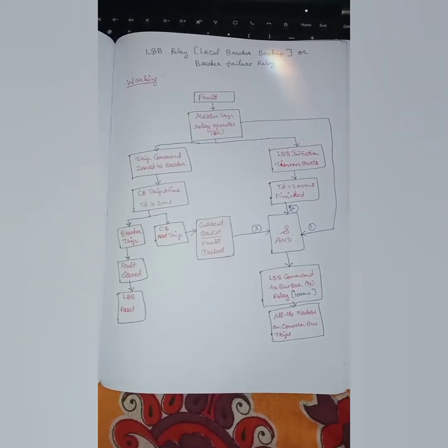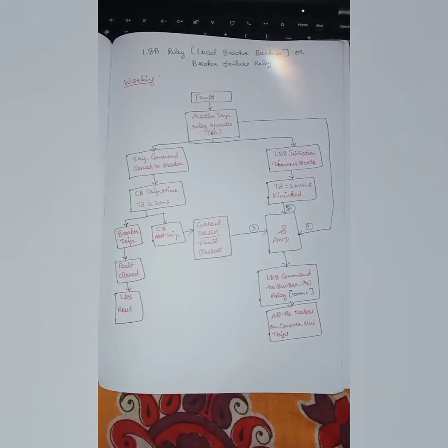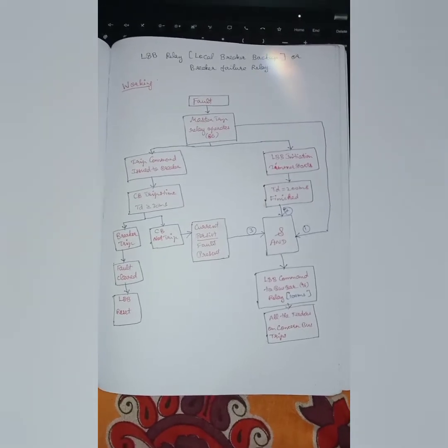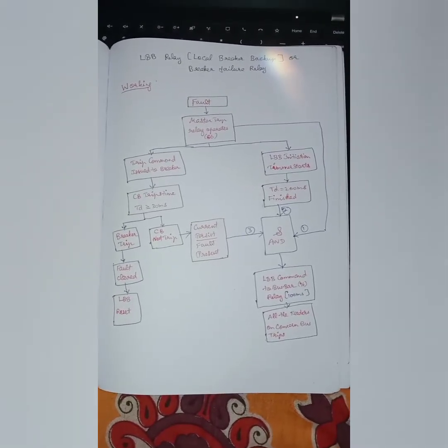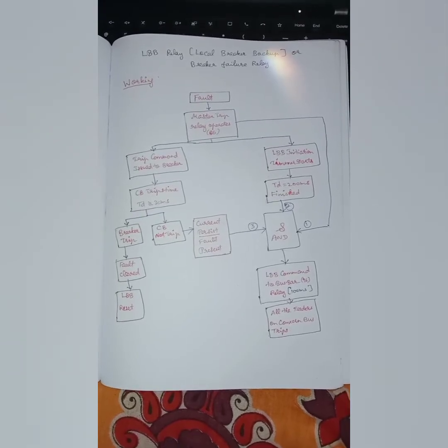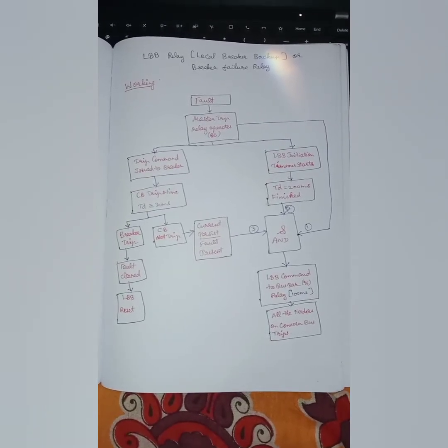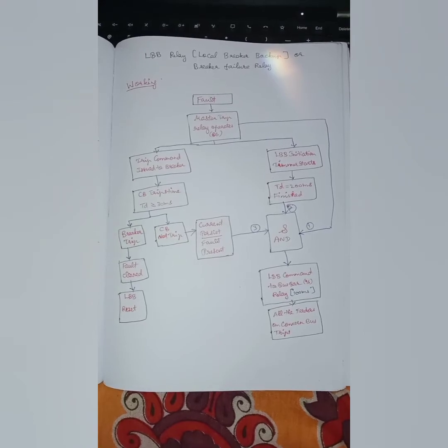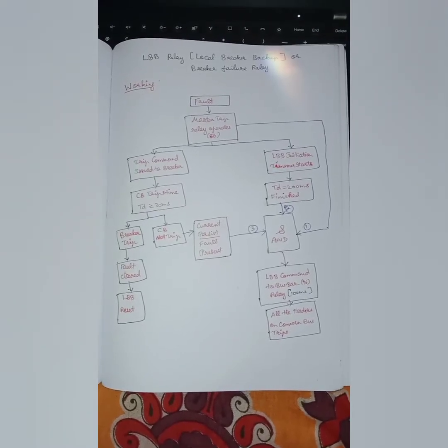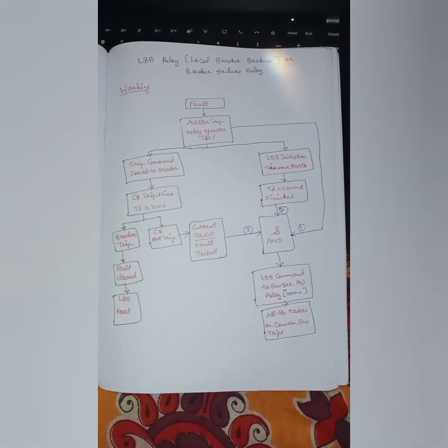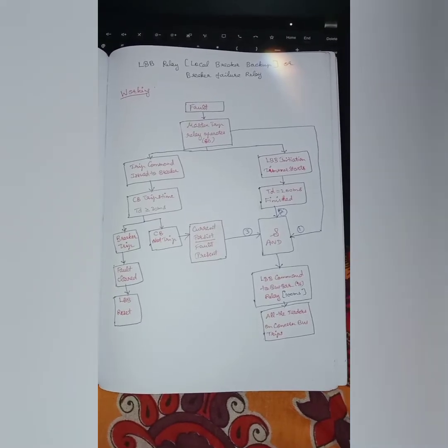Whenever a fault occurs due to some breaker failure, or any loose contact in your trip coils, or any internal damage in your breaker, the breaker will not be able to operate for that internal fault. Once the fault has occurred, your master trip relay senses it and initiates a trip, and as the trip relay gets involved, automatically the tripping coil should get energized and give a trip signal to your breaker, and your breaker should open.